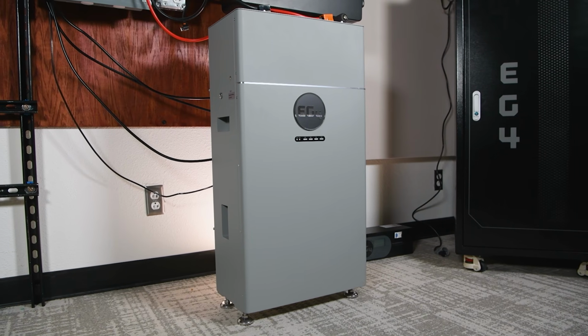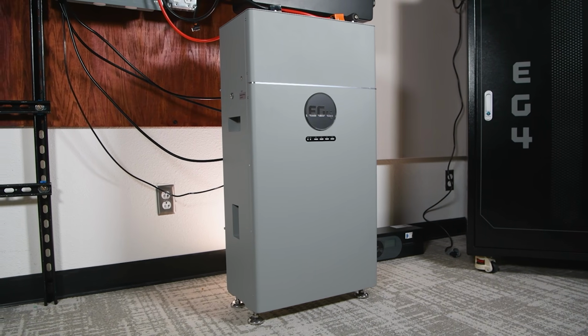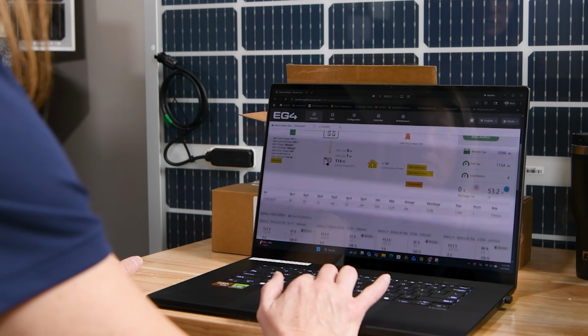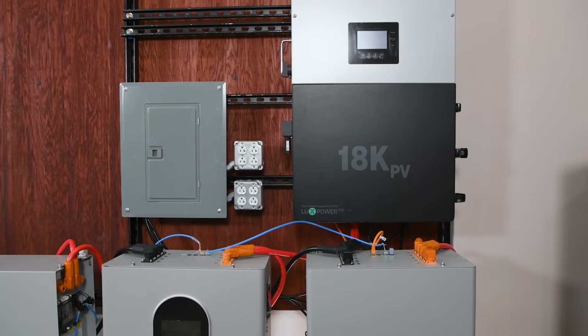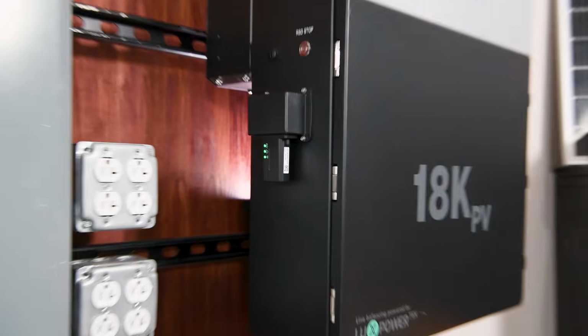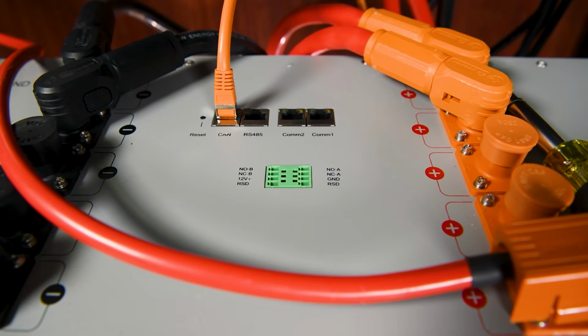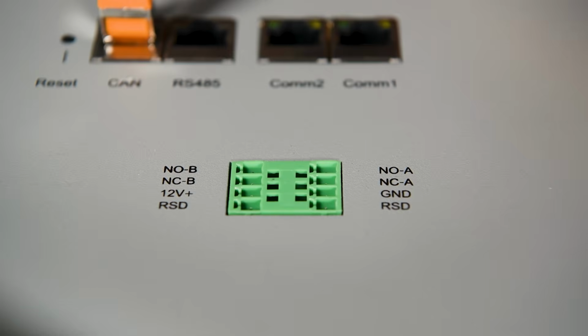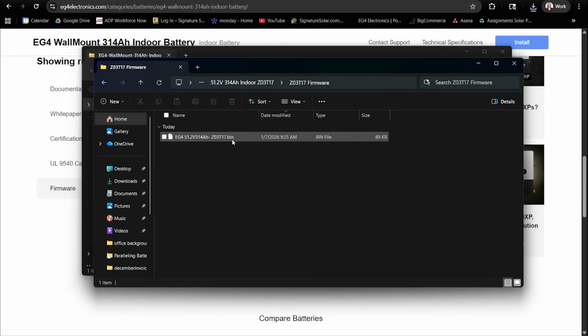And that's the complete OTA firmware update process for the EG4 wall mount 314 amp hour indoor battery using the EG4 Monitor Center portal. The key things to remember are making sure your hybrid inverter and Wi-Fi dongle are fully updated first, disconnecting all dry contacts before starting, verifying the correct firmware file, and never interrupting power once the update begins transferring to the battery.